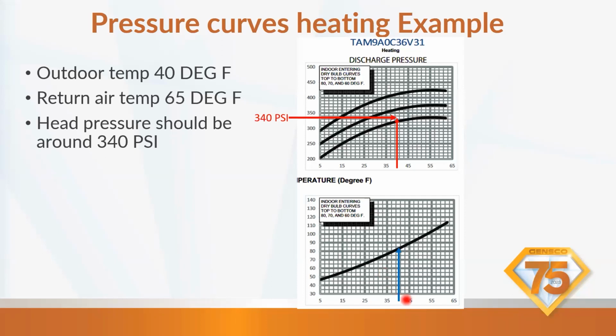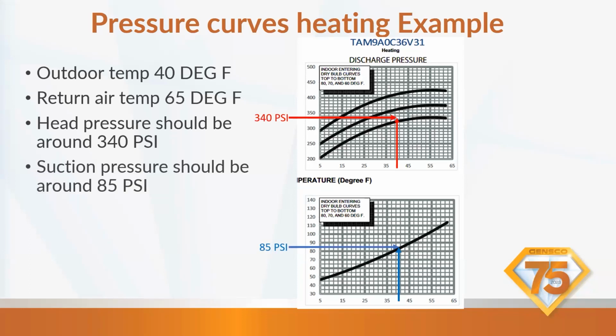We go down to the suction side, 40-degree ambient. Where does it intersect with the line? Right about 85. So now we have a head pressure of 340 and a suction of 85. Your pressure is going to be plus or minus 10 of the PSI chart. So again, this is to get you close. So if you are close to these lines in heating mode, we're feeling pretty confident that we have a charge that's going to get us through heating until we can come out during springtime, summertime, when it's above 55 degrees ambient. But again, I've used this on other systems. So if you're under, you're going to add refrigerant. If you're over, you're going to remove refrigerant.